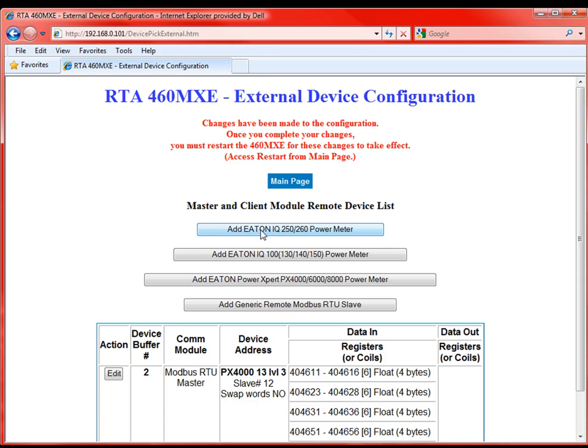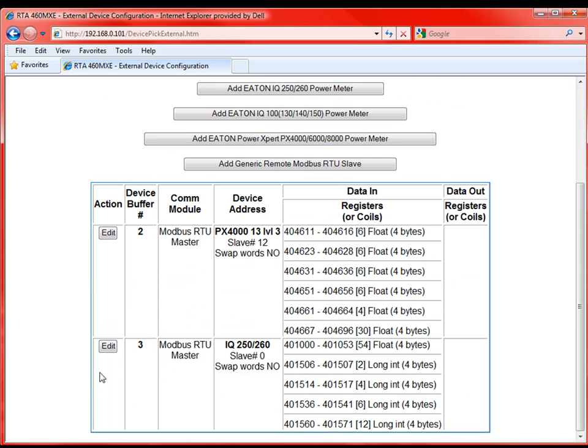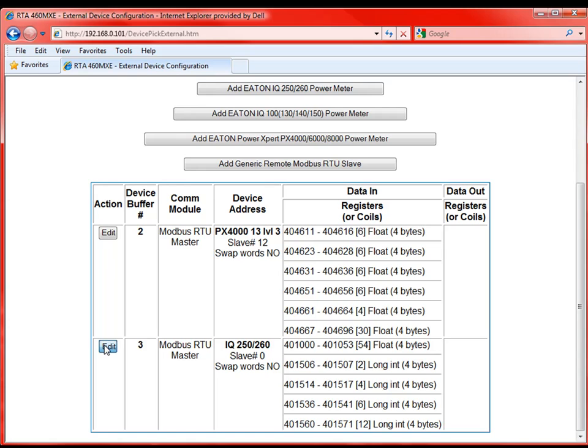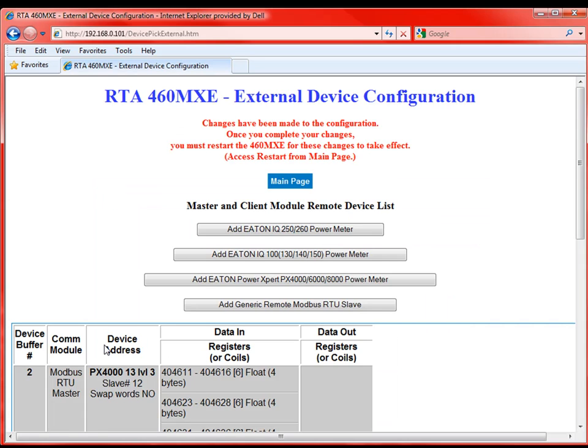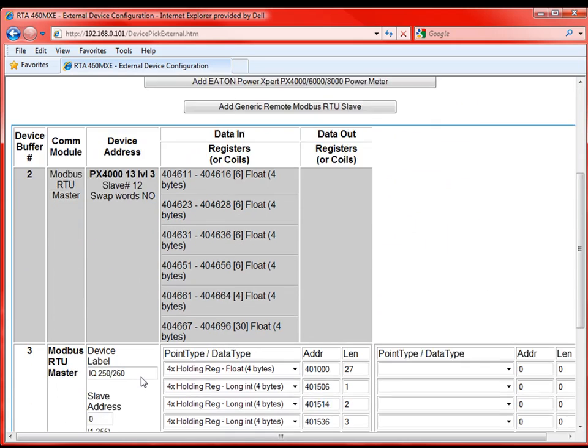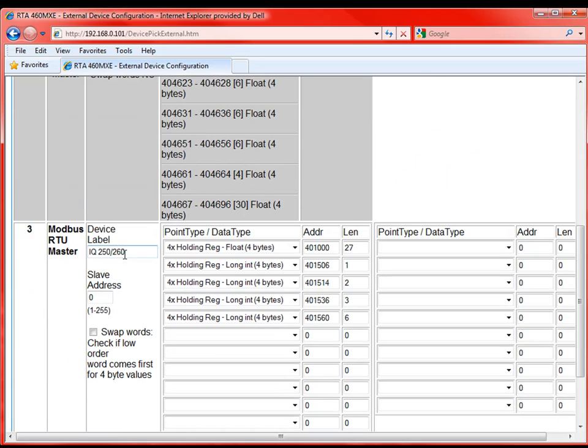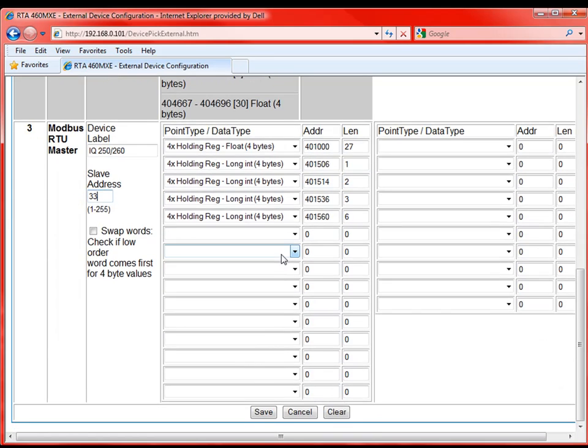Let's just for the sake say we also have an Eaton IQ 250-260. Same exact setup, we're going to add that device. We're going to go down and we're going to edit that. So as we can see right now it's just the IQ 250-260. This slave address, this slave is number 33. And here again it has pulled registers from that device that 90% of the users have needed. So again we've just added our second slave device and we'll hit save.